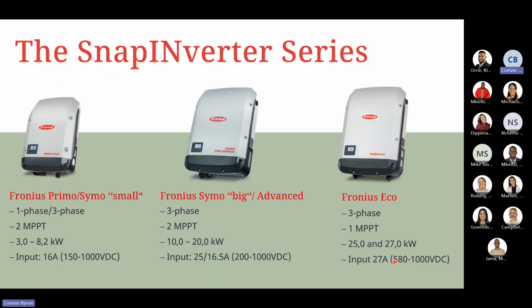So the input range is 580 to 1000, but what to keep in mind on these units is the usable range. So for example, on the Simos, it's from 350 upwards, 400 volt DC upwards. Whereas on the Ecos, it's 650 volts and above is the usable range. So we typically advise clients to keep within 650 and 1000 of the unit in order to make sure that you are in the usable range of the unit.